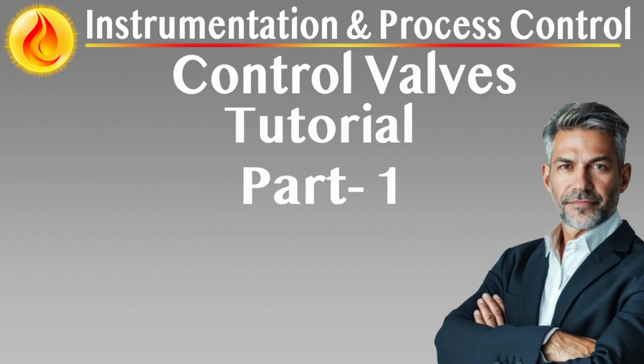Clean fluid service is mandatory for all balanced trim configurations, and their use requires prior approval. Trim construction requirements. Rotary and linear valve trims must feature easy, quick replaceable plug and seat ring assemblies. For welded end valves, all trims, including seats, must be removable from the top of the valve to support inline maintenance. Where trim construction is not integral, i.e., separate plug and stem, a locking mechanism is required to prevent disconnection and stem blowout. This locking feature must not breach the valve pressure boundary.